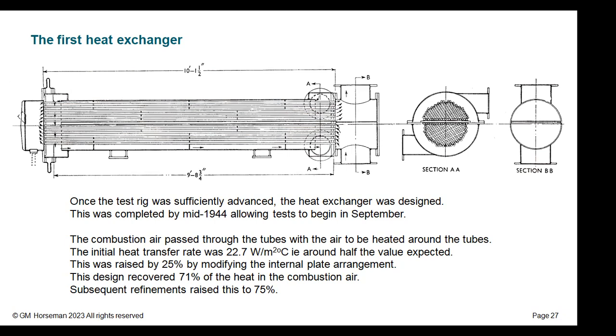They changed the tube support plates, which guided the gas flow, and improved it by 25%. So the heat transfer coefficient was a little low, but it did recover 71% of the heat in the combustion air. So it wasn't far off target. And as a very first attempt at building an exhaust heat recovery device, that wasn't too bad. Now, subsequent refinements did raise it to the 75% level. I haven't put them on screen because you wouldn't be able to tell the difference much from what you're looking at now. It would be a 2-pass tube and shell heat exchanger.